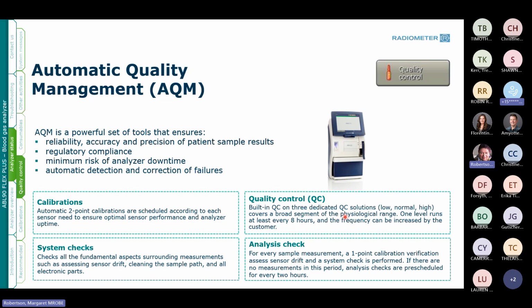Built-in quality control, we've talked about those. There are 3 dedicated quality control solutions that come out of the solution pack. One control runs every 8 hours. The frequency can be increased by the customer if you choose, and we can set that as well, so if you need to do some changes there. And then the analyzer's sample measurement: a 1-point calibration verification assesses sensor drift in the system each time you do a patient sample.